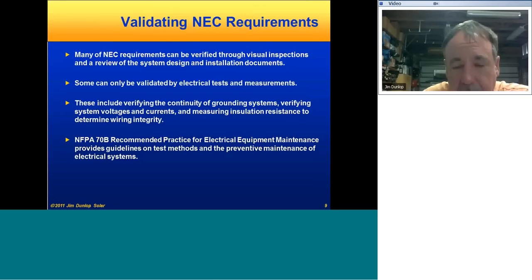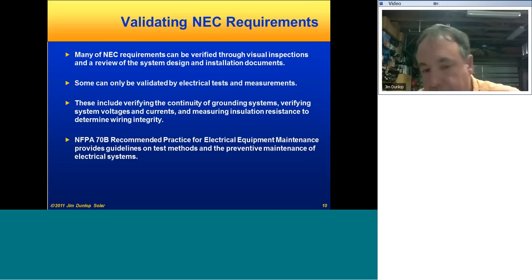One of the things that is striking about the code requirements, there's a lot of things that you can do in validating NEC requirements for a system through a plan review and reviewing the design and then obviously a visual inspection of the installation. There's some things that are NEC requirements that really can only be validated through tests and measurements. And a lot of these things aren't done for most PV installations, but probably should be, and that's some of the things addressed in the standard. We're talking about the continuity, resistance of grounding systems, grounding electrodes, verifying voltage and currents, operation, short circuit, open circuit, that sort of thing. Recording those measurements and keeping those in the permanent record for the system. Measuring insulation resistance, determine the integrity of the wiring systems. That can be done on various circuits in the array as well.